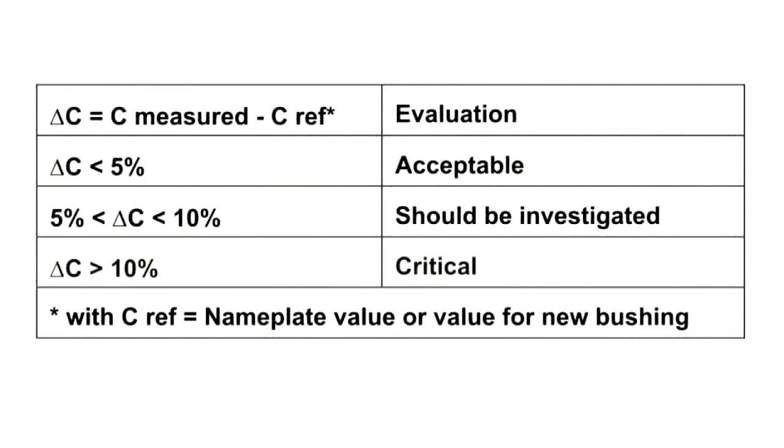For resin bonded paper bushings, cracks into which oil has leaked can also change the value of the capacitance. A rise in capacitance of more than 10% is normally considered to be dangerous since it indicates that the insulation distance is no longer sufficient.